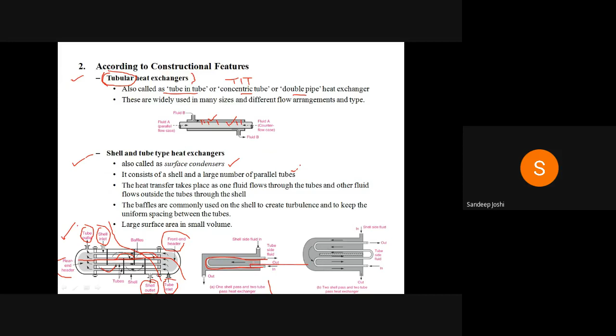In the shell and tube heat exchanger also there are different types, right? It depends on how many shells are there, and how many tube passes are there. Based on that, there is another classification. Some classifications are shown here. This is one classification: one shell pass and two tube pass heat exchanger. You can see this is the one shell, and two tube pass means this is pass 1 of the tube, and this is pass 2. That's why this is called a double pass or two tube pass. And as there is a single shell, I will call this a one shell pass two tube pass heat exchanger.